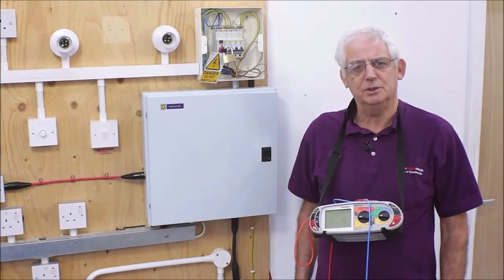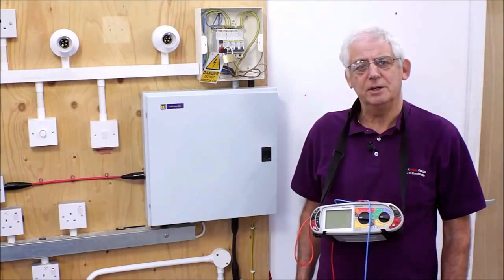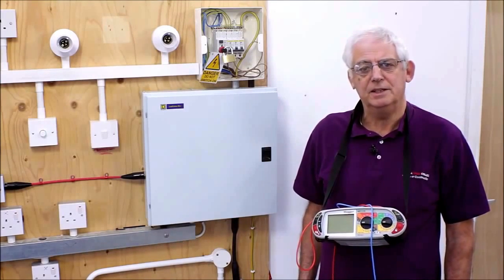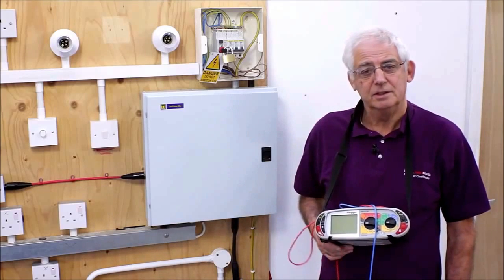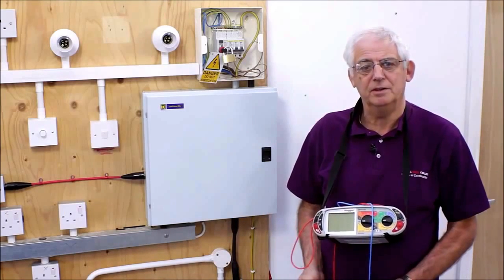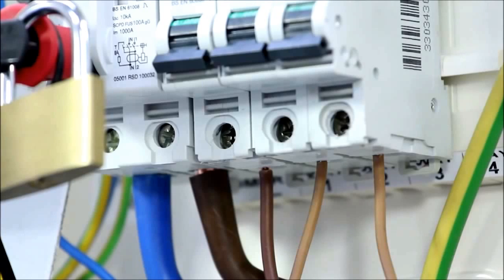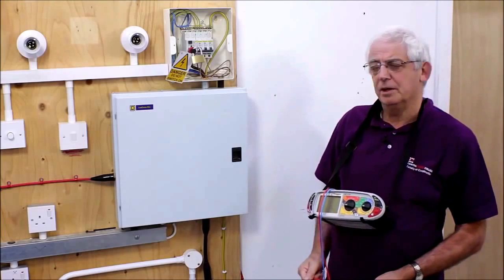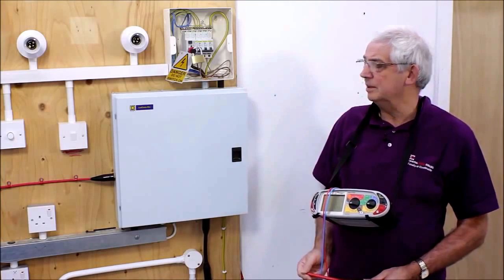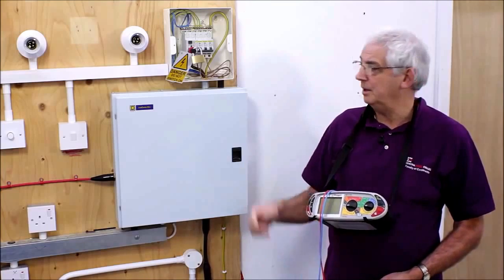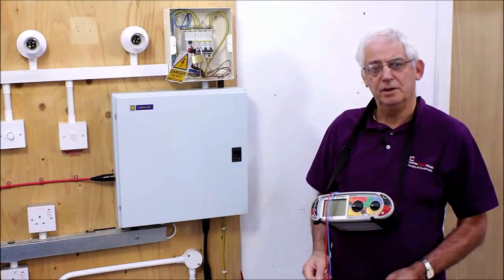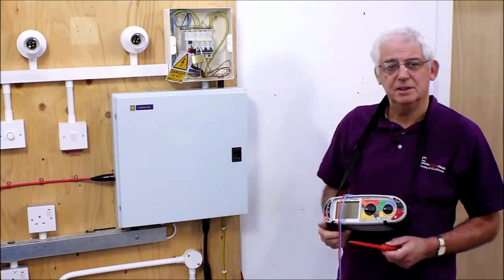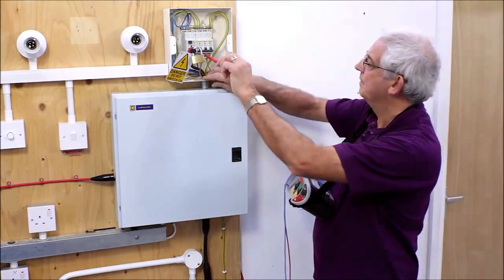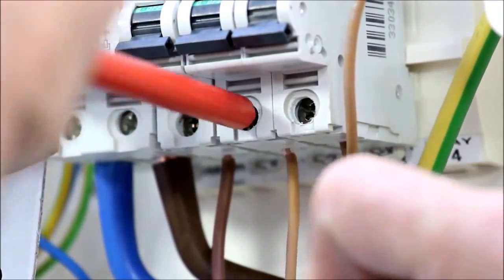We're going to do an R1 and R2 test on a lighting circuit, and at the same time prove that we've got polarity. In other words, that the switch is in the line conductor, which obviously is part of our inspection. You can see I've got the board locked off. It's nice and safe. I can work on it. There's notices. What I need to do to get an R1 and R2 test is to join the line conductor of the circuit I'm testing with the earthing conductor. So the easiest way really is just to disconnect it and put it into the earth bar of the board. There are other ways, of course, but in this instance, this is probably the easiest.